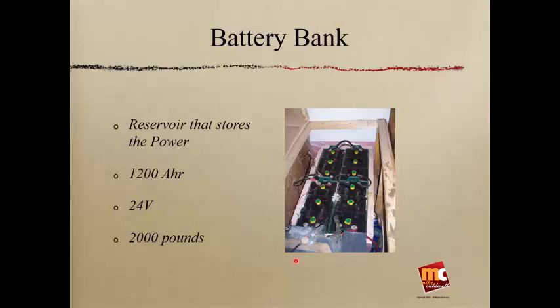One thing about batteries, though, is they can't put out as much power when they're cold, and unfortunately, these batteries are stored downstairs in a 2,000 square foot area with a big concrete floor. So that room gets to be about 6 degrees Celsius, maybe even down to 4 degrees Celsius. So it can be a bit cold down there, and so in the winter, the batteries struggle a little bit more, especially as they're getting older. But like I say, I've been going for 11 years now, and the batteries are doing great. They don't seem to be showing too many signs of slowing down.